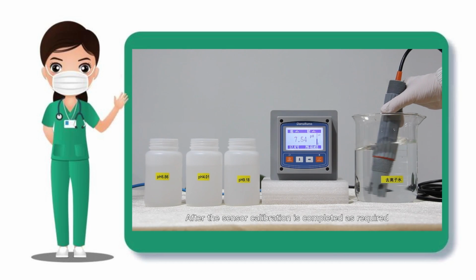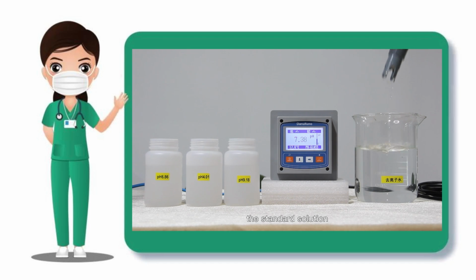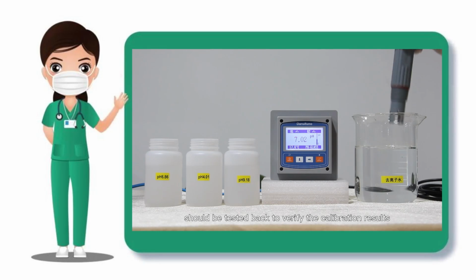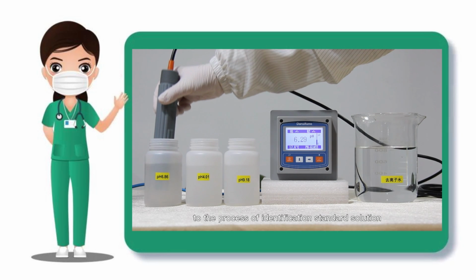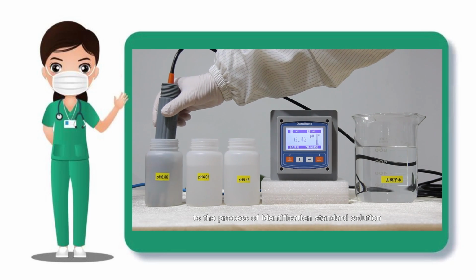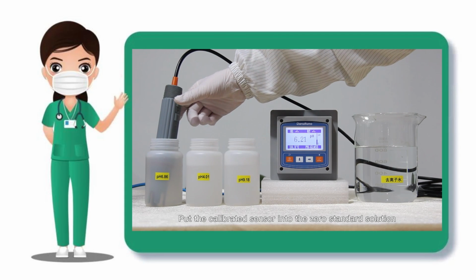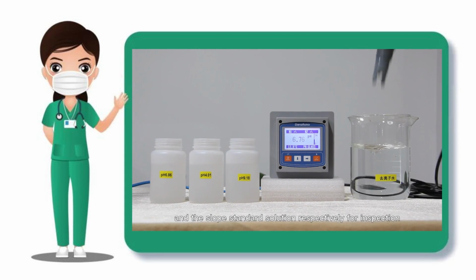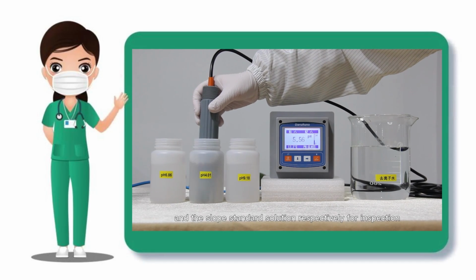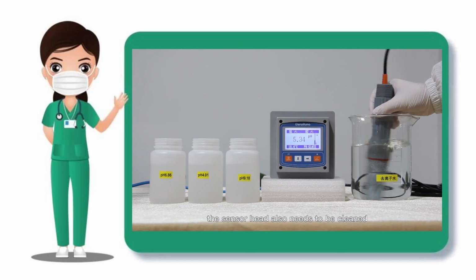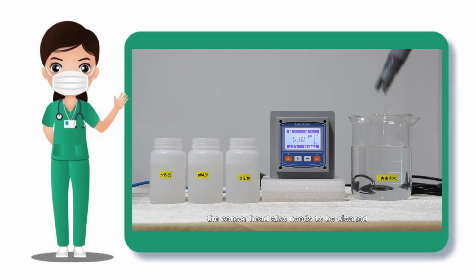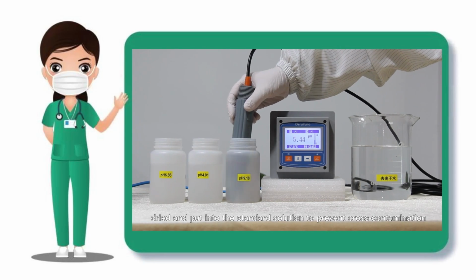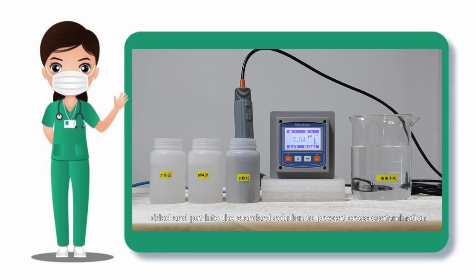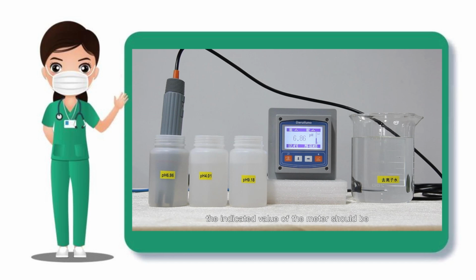After the sensor calibration is completed as required, the standard solution should be tested back to verify the calibration results. The process of backtesting is similar to the process of calibrating with the standard solution. Put the calibrated sensor into the zero standard solution and the slope standard solution respectively for inspection. During the process, the sensor head also needs to be cleaned, dried and put into the standard solution to prevent cross-contamination.